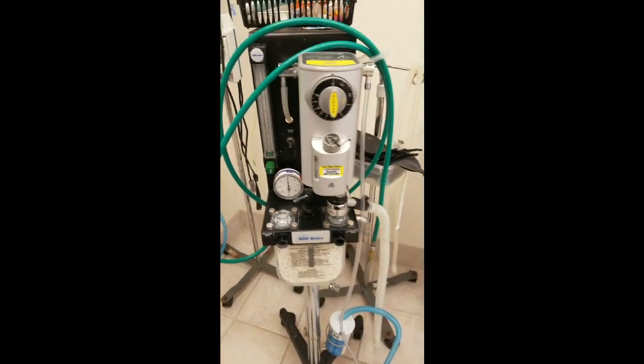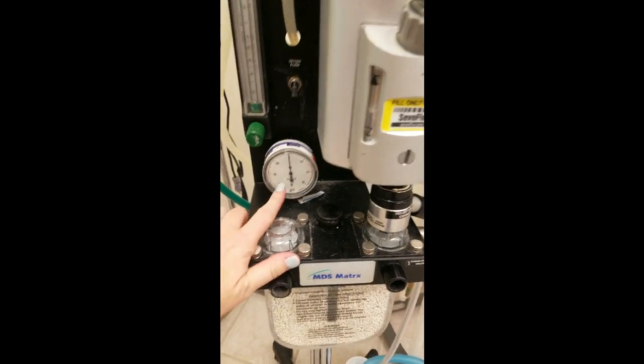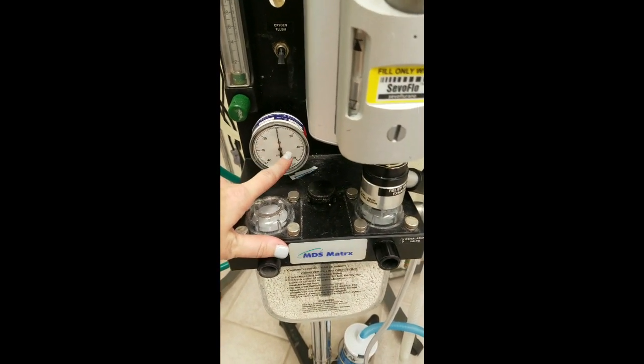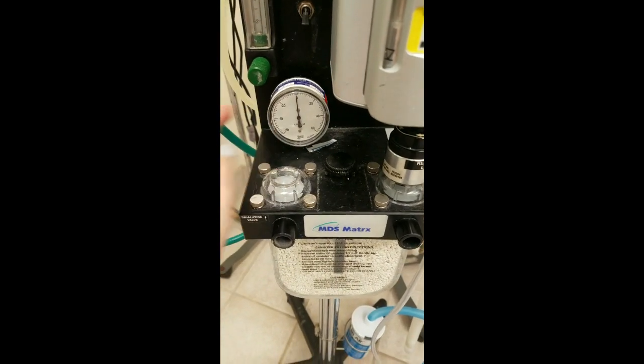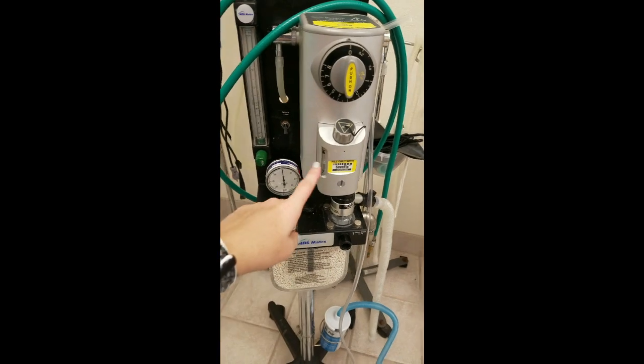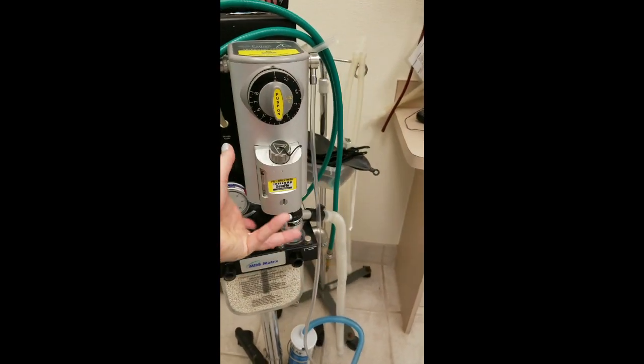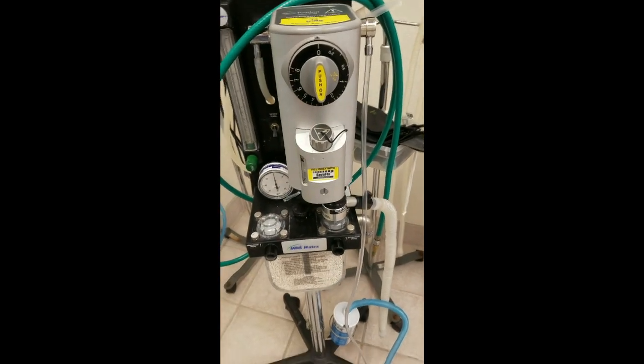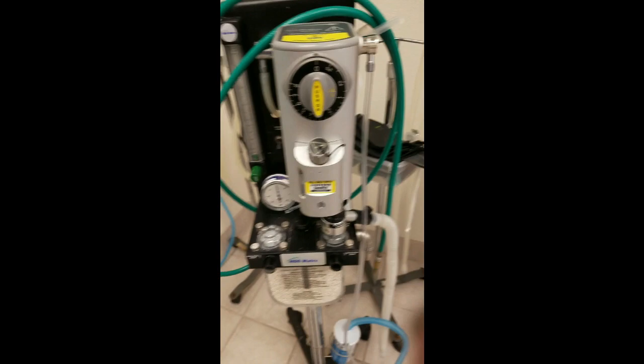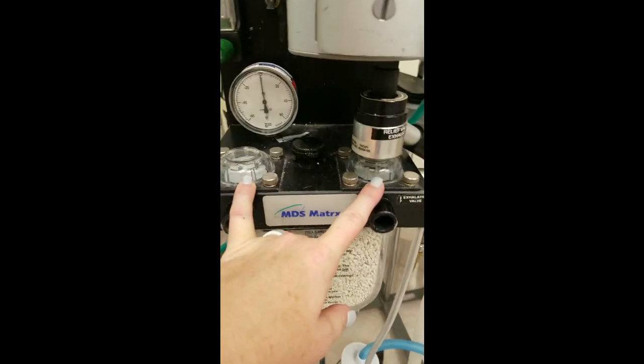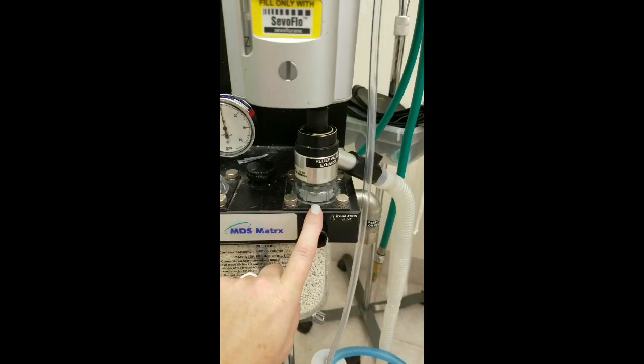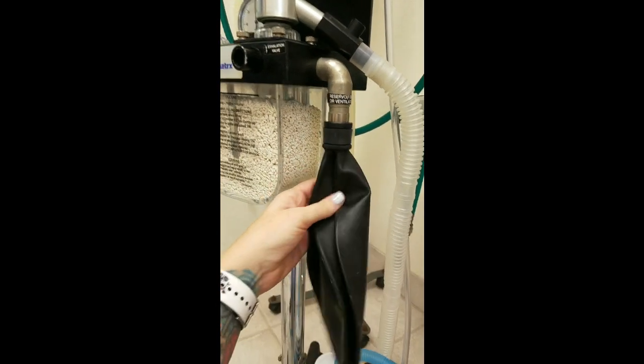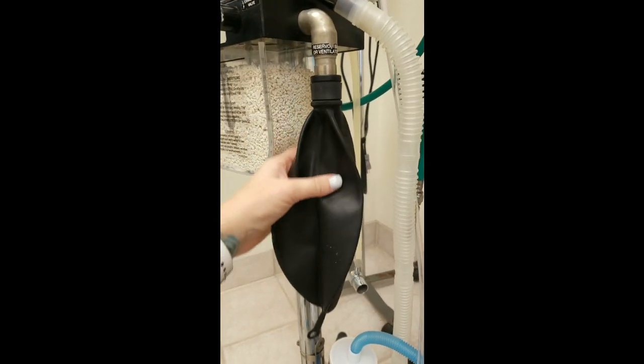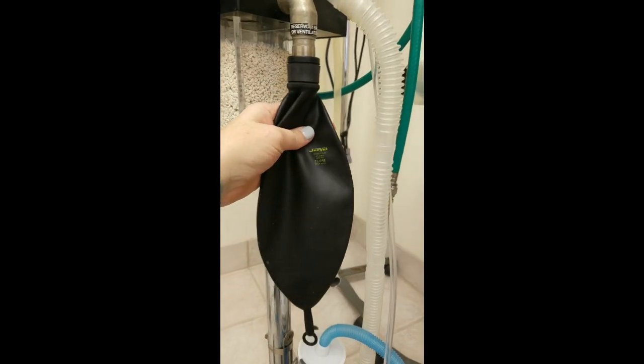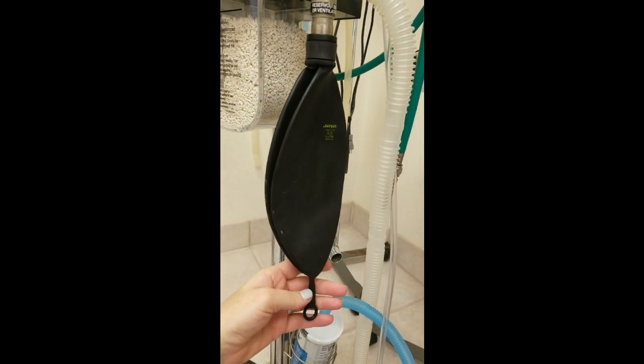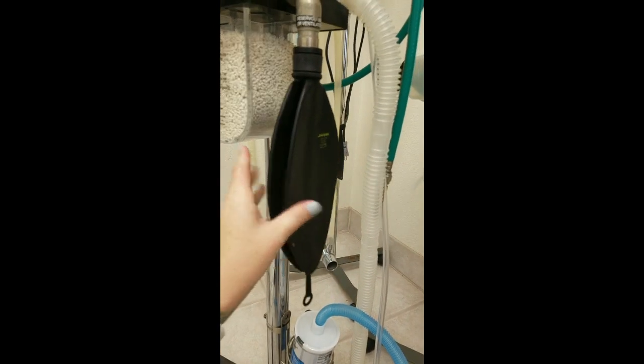So this is our anesthetic machine, and some of the parts on it. This is our pressure meter, and this is going to let us know the pressure in the patient's lungs. And this is the vaporizer. So this contains our sevoflurane, and this is going to take it from a liquid form and turn it into a gas to pump it through to the patient. And these are our flutter valves. This is the inhalation, exhalation, and this is our reservoir bag. The bag expands and contracts with the patient's breathing, and this also allows us a way to monitor their breathing because we'll see it inflate.